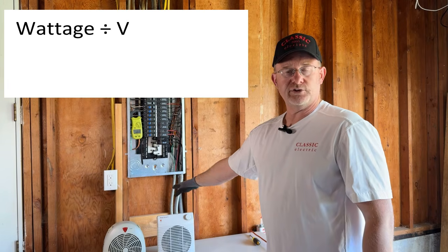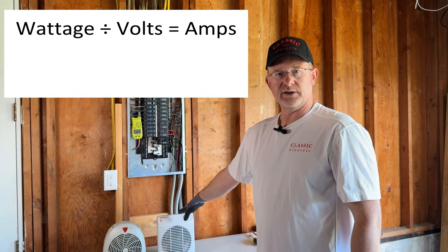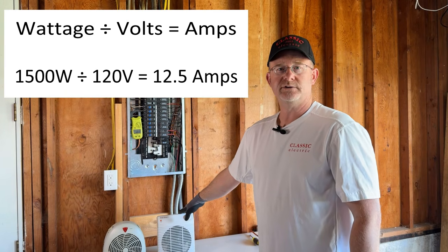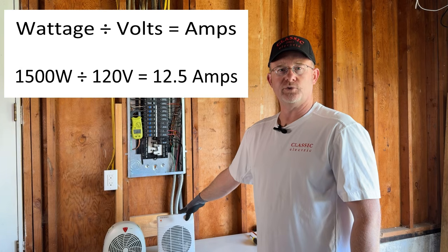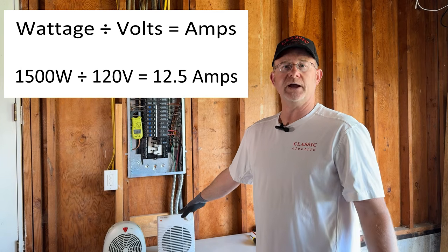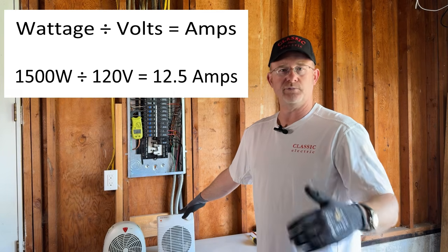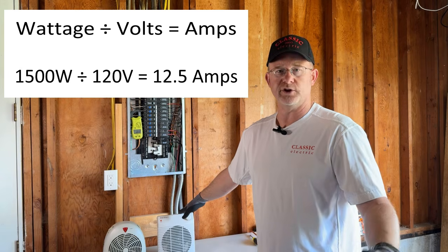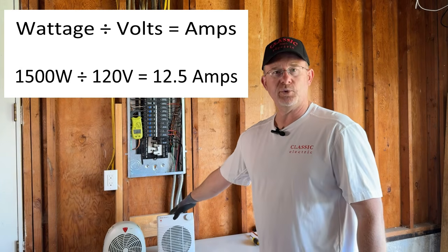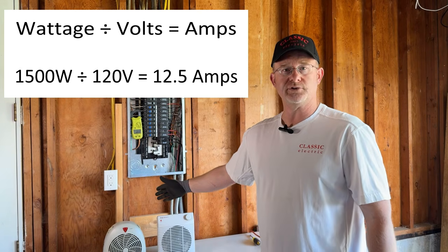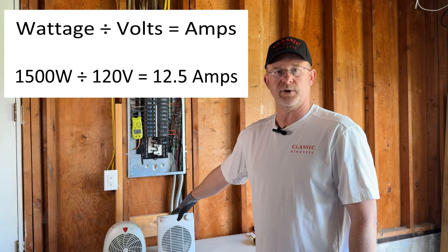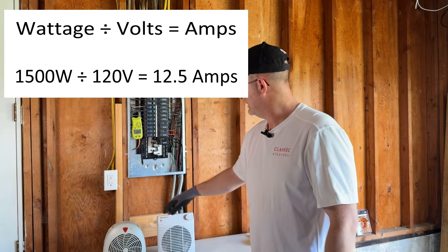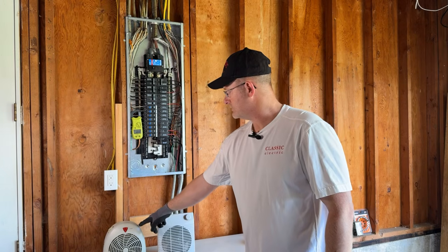So if it doesn't give it to you in amps, what I do is I take 1500 watts, I divide it by 120 volts, and that's going to give me my amperage. It's just a basic Ohm's law calculation that electricians know. And that answer is going to be 12.5 amps. So let me prove it to you in real time that this thing really does pull 12.5 amps. So watch this. So we're going to turn on this heater right here.